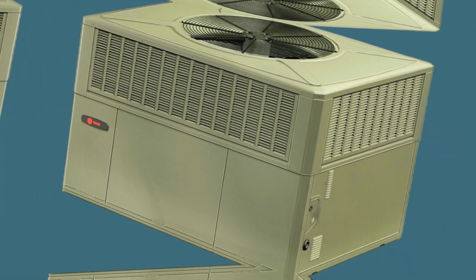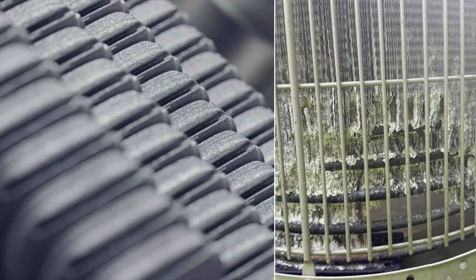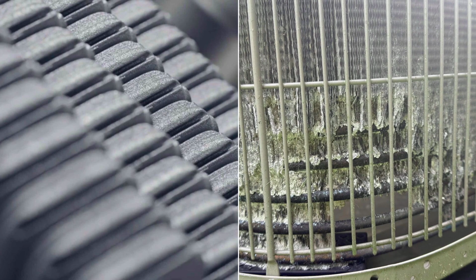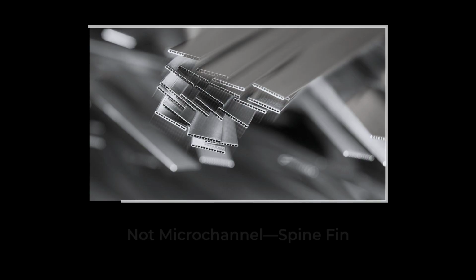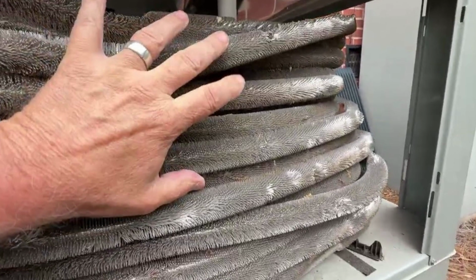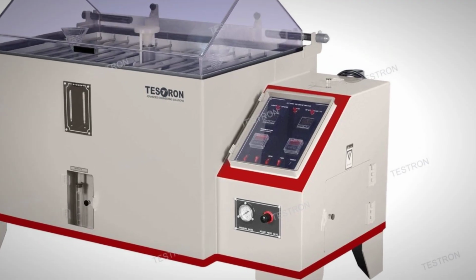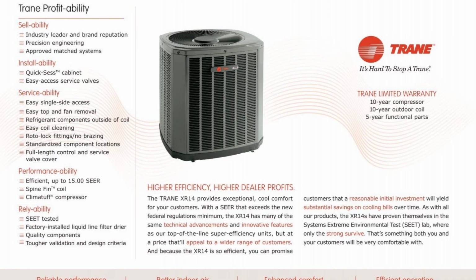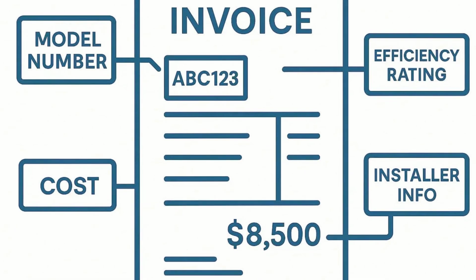Trane and American Standard market their spine fin coil design as an all-aluminum alternative to conventional copper aluminum construction, but critically, it is not flat-port microchannel. Spine fin uses continuous aluminum tubing with bonded spine-shaped fins wrapped around the tube rather than the dense multi-port channel geometry that creates the repair nightmare. The design resists corrosion differently. The marketing materials brag about durability and longevity instead of hiding the coil construction behind efficiency jargon and rebate qualifications.